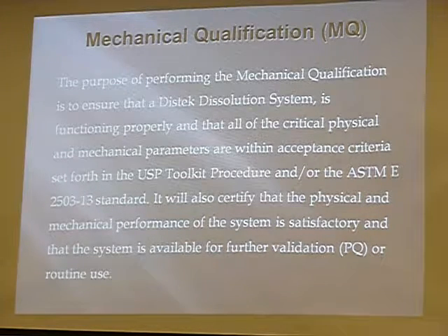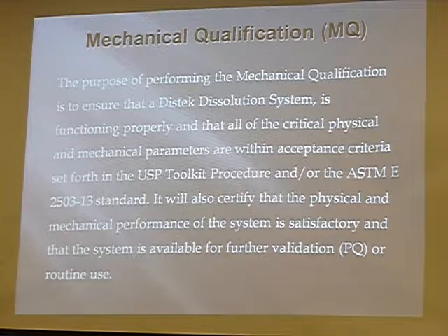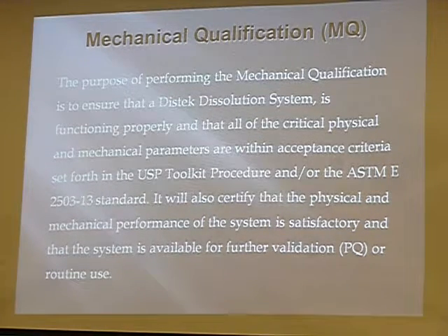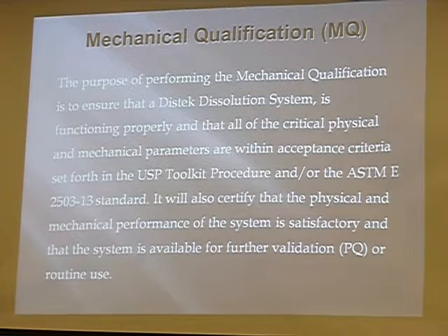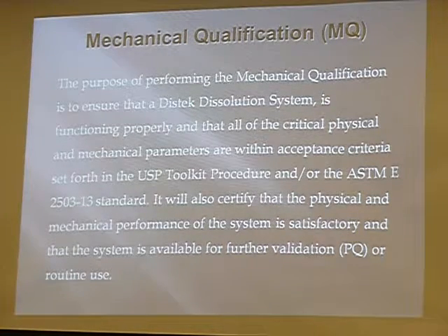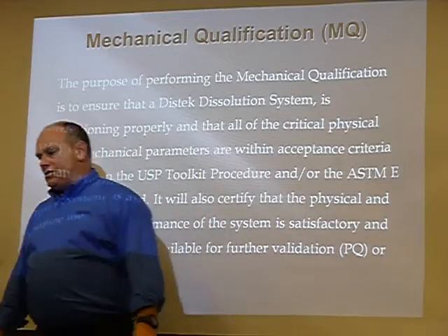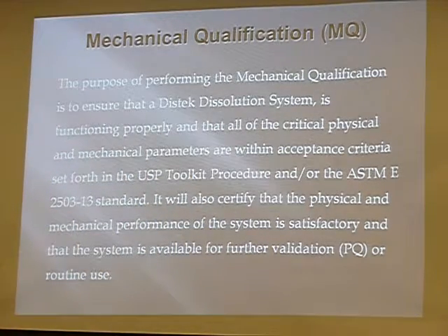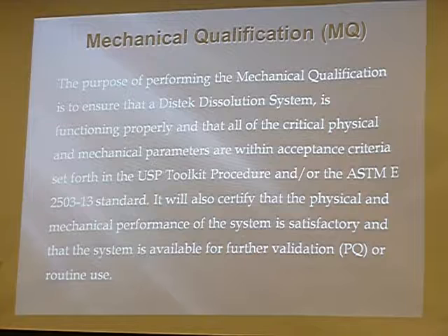Two different ways of validating. About 5 years ago, a lot of laboratories got together and were complaining about the way the calibrator tablets were, that USP was kind of, I don't know, monopolizing the industry, making everybody adhere to their particular standards. So the FDA partnered with ASTM and came out with a mechanical qualification, hence the ASTM E2503-13. It basically is a tighter specification mechanically, because in their mind they figured if you have a tighter mechanical specification on a set dissolution bath, then theoretically, chemically, it should work automatically. So they came out with a competing standard, so to speak, that doesn't require any calibrator tablets.